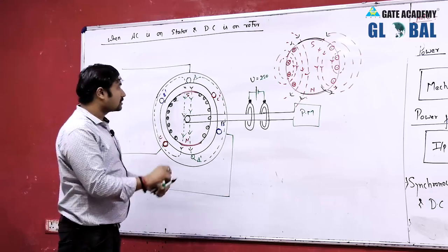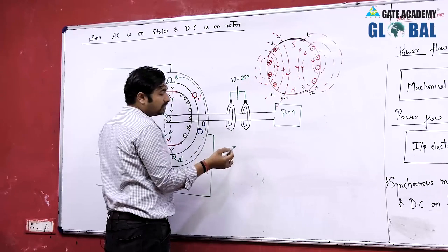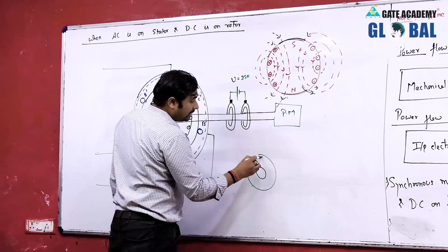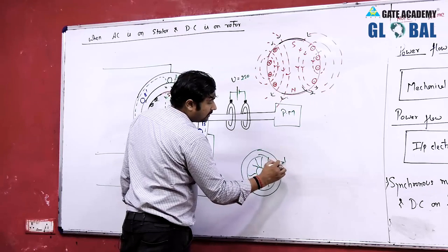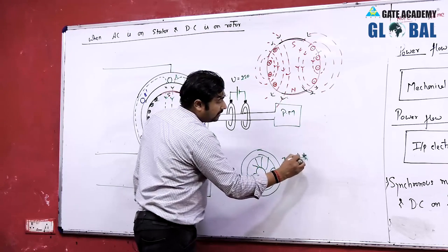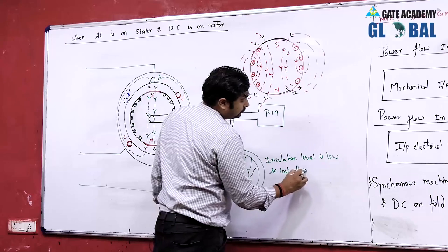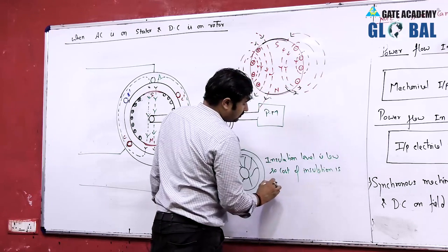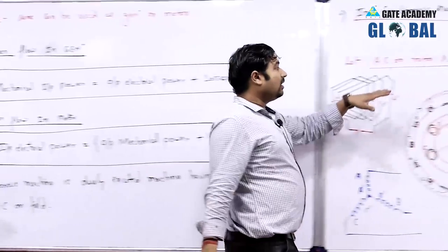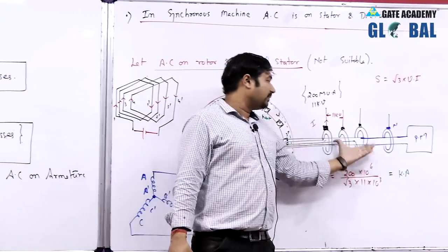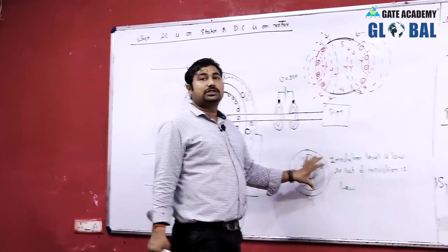The voltage needed on the slip ring is only about 250 volts, so the slip ring size and insulation cost needed will be lower. In the previous case — DC on stator, AC on rotor — we needed 4 slip rings; in this case, we only need 2 slip rings and the insulation cost is also lower. Overall cost of insulation decreases, centrifugal force is lower, and the most important advantage is effective cooling.